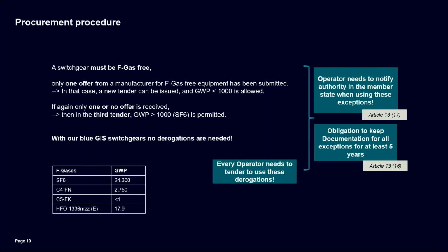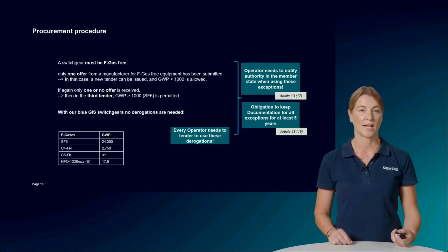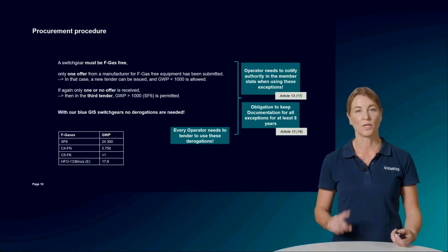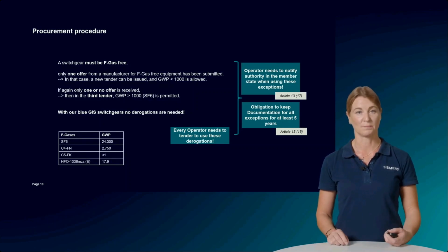If these conditions are not met, the following procurement cascade can be applied. Starting from January 2026, a 24 kV switchgear must be F-gas-free, unless only one offer from one manufacturer of F-gas-free equipment has been submitted. In that case, a new tender can be issued and a GWP smaller than 1000 is allowed. If only one or no offer is received, then a third tender with GWP above 1000 is permitted.